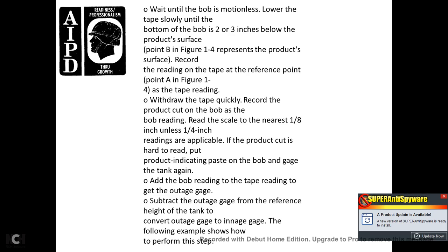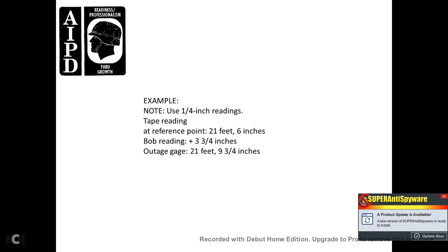39. Withdraw the tape quickly, then record the product cut on the bob as the bob reading. Read the scale to the nearest one-eighth of an inch; if less than one-quarter of an inch, use the applicable reading. If the product cut is hard to read, reapply the product indicating paste to the bob and gauge the tank again. Add the bob reading to the tape reading to get the total outage gauge. 40. Subtract the outage gauge from the reference height of the tank to obtain the ingage. Convert the outage gauge to an ingage using the following procedure.